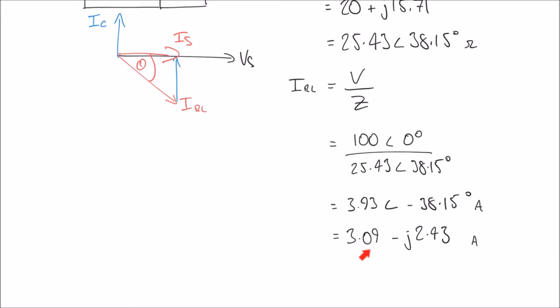The current drawn through the RL branch — the motor in reality — is 3.09 minus j2.43. The 3.09 amps is what we call the real current, and the j term, minus 2.43 amps, is the reactive current. On the phasor diagram, IRL's real current is the horizontal component and the reactive component of minus 2.43 is pulling downwards. So we want our capacitor to draw plus j2.43 amps to cancel out the minus j2.43 reactive current in the RL branch.